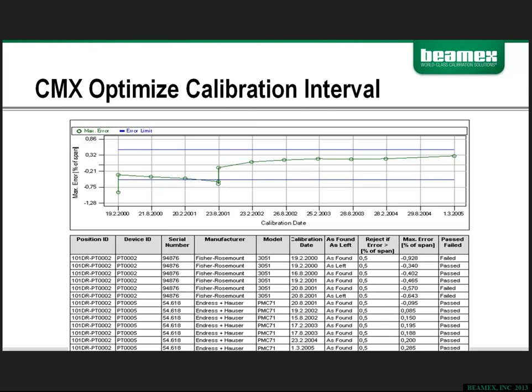They identified through analysis the need for replacement of the Fisher-Rosemount device, and they've also identified that the Endress+Hauser, at least in this particular position, has performed very well over an extended period of time. So in the future, it would probably be better to put another Endress+Hauser device in another location in the plant with similar characteristics based on the data that was collected and analyzed through this one history trend analysis.